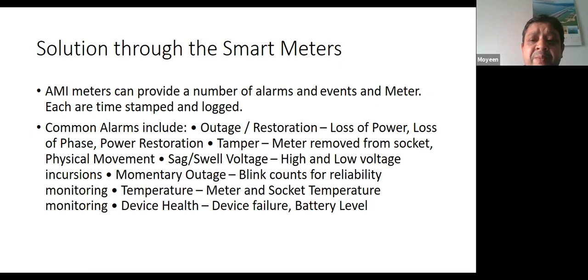A smart meter, as I'm showing, can provide alarms and events, and you can timestamp and log the data inside the system. When the power goes out, you can always know whether power has gone, when it is restored - the phase, the power restoration, tampering, somebody playing with the meter. It can also log the voltage profile - whether voltage is below 160, 150, or so - these kinds of things are also logged and sent back to the IT system, along with temperature, device health. So all these events are coming from smart meters.